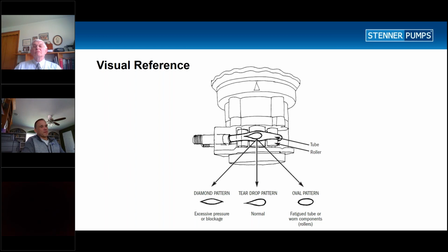Now, when you look at the pump, this is the most common question that comes up: how do I tell if the tube needs to be replaced? On the outside of the housing of the pump, you can do a visual inspection without taking the head apart. If you see a teardrop pattern, then you know that the tube's in good working order. Anytime that you see a diamond or oval pattern or some other type of shape on the tube going through the tube housing, we'd recommend replacing the tube.